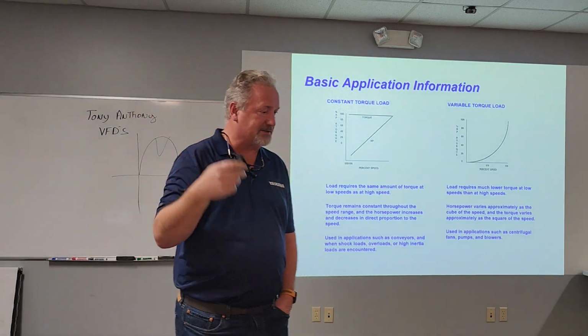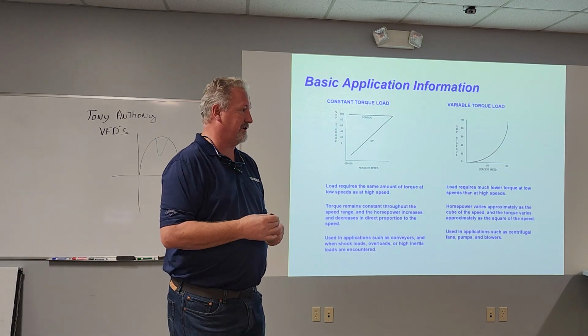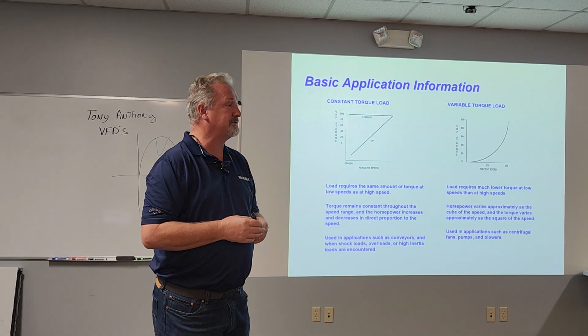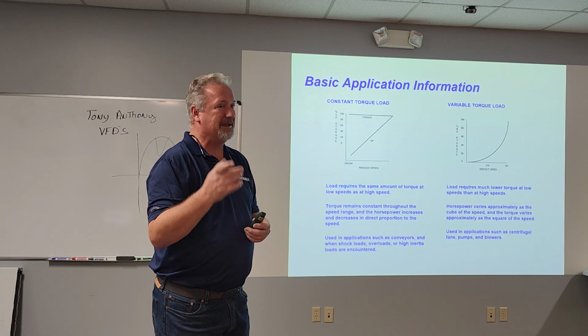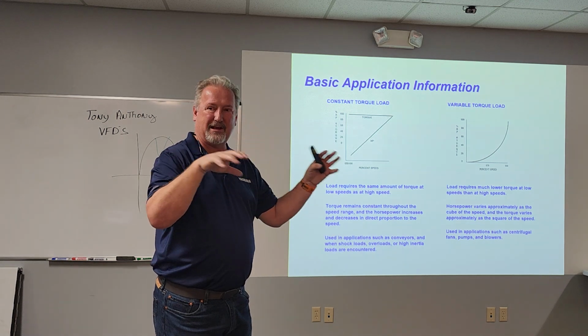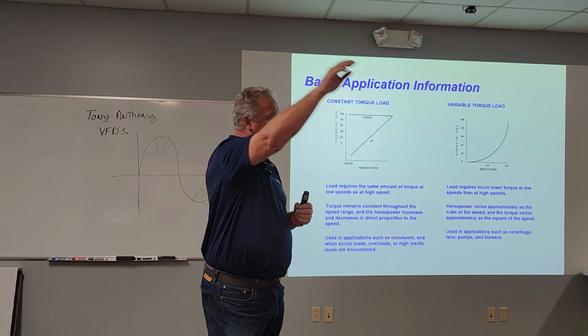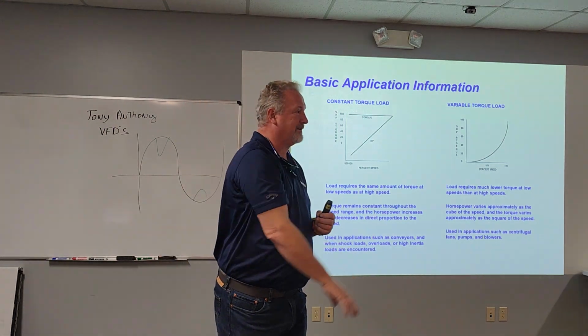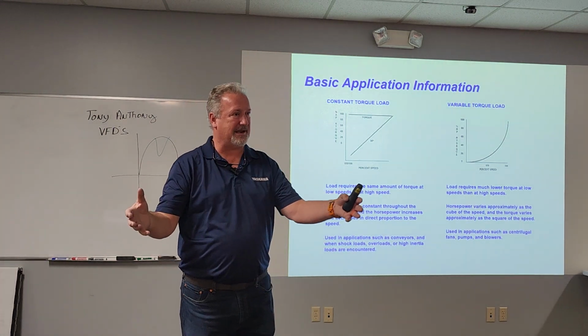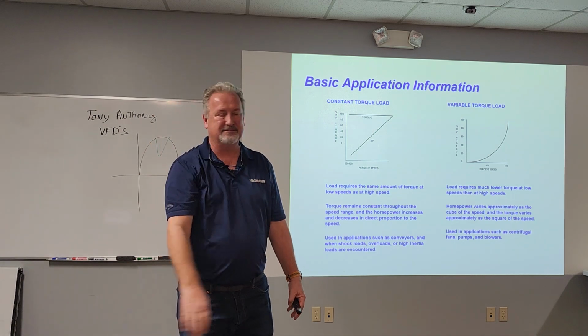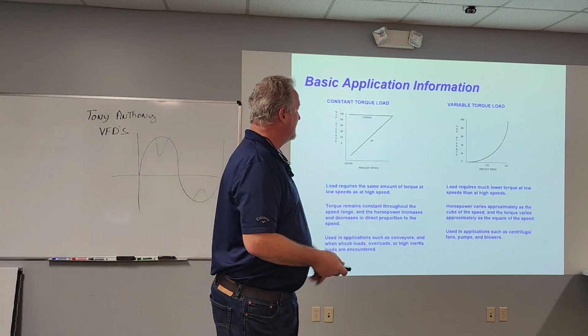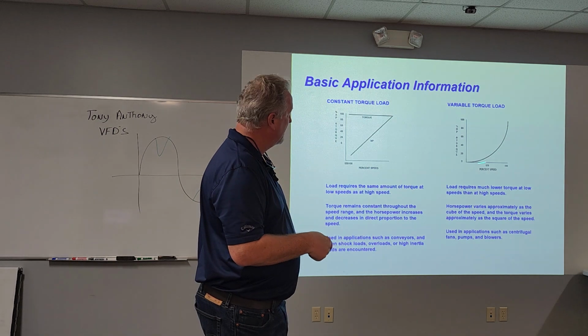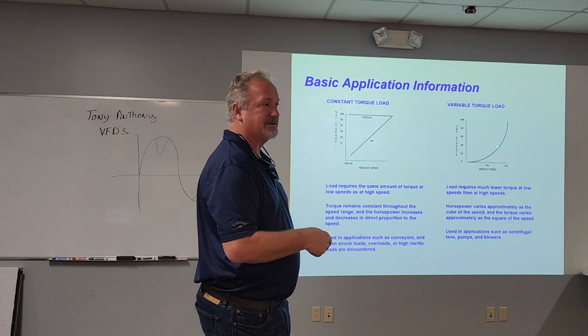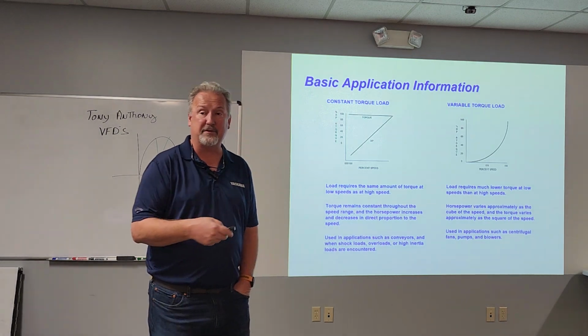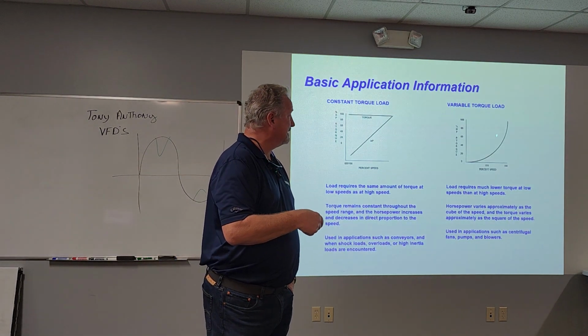In the Liberty Tunnels in Pittsburgh, my drives are on the fans in those tunnels. Those fans are about 10-foot diameter. After they put the new fans in, before they had the covers and everything on, you could literally walk up with your hand and turn those 10-foot diameter fans like it was nothing, because once they had them balanced, all you were doing was overcoming the friction of the bearings. Doing no work. That's why variable torque loads down here take almost no torque to get a fan going, because it's not moving any air. Same thing with a pump. We're not moving anything, so to get it going doesn't take much.